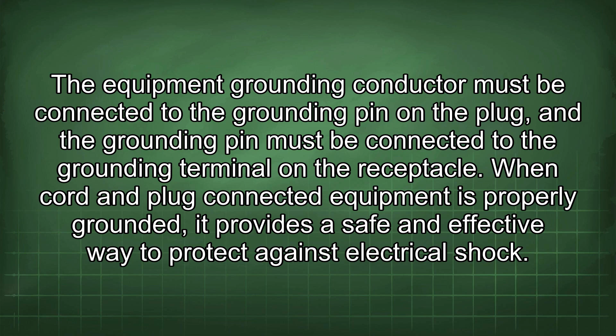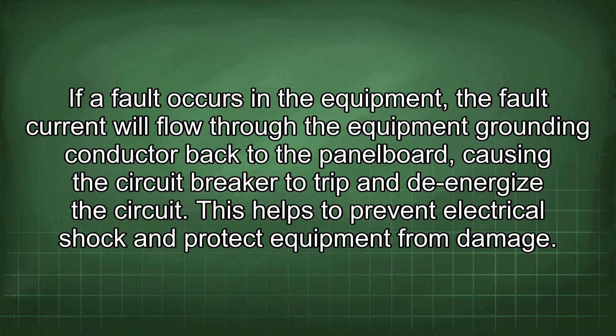When cord and plug connected equipment is properly grounded, it provides a safe and effective way to protect against electrical shock. If a fault occurs in the equipment, the fault current will flow through the equipment grounding conductor back to the panel board, causing the circuit breaker to trip and de-energize the circuit. This helps to prevent electrical shock and protect equipment from damage.